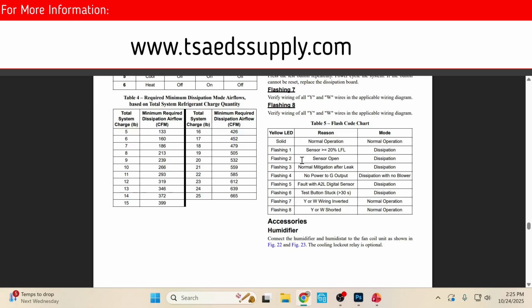leak, you're going to sense that this part here, the sensor, has reached 20% of the lower flammability limit in that unit. So you've got to figure the air handler itself, where the coil is, is considered 100%. So that sensor has picked up that 20% out of that 100% space. There's a leak. Now here's why I was telling you the airflow is so important.